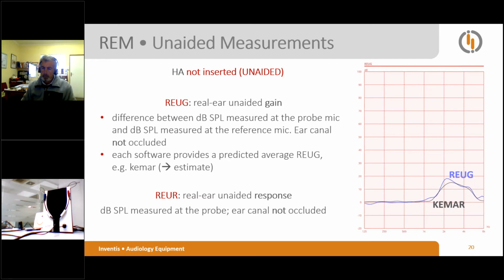Anyway, to acquire a real ear unaided gain curve, okay, the user can choose whether to use a white noise or a pink noise that will be sent by the speaker at a predetermined intensity. The choice to display, together with the measurement, the predicted average real ear unaided gain can be a useful reference, I would say, to verify in real time if the signal being acquired is reliable. Otherwise, the probe tube may not be inserted properly. In this situation, it is possible to change the placement of the probe tube until the two curves are compatible.